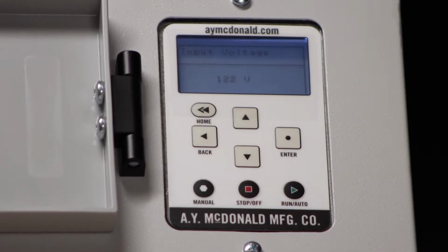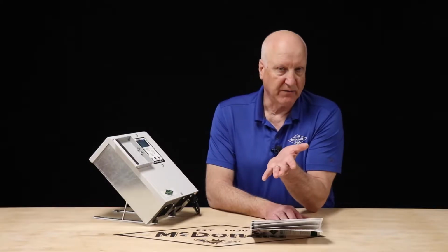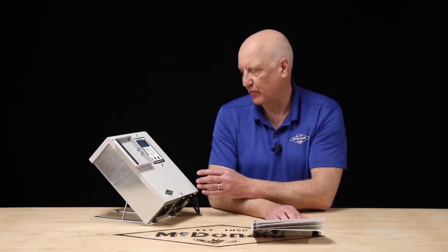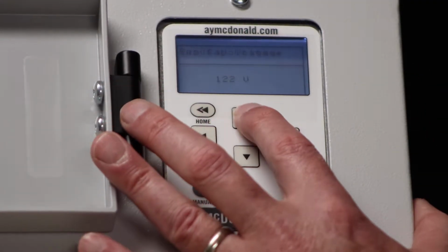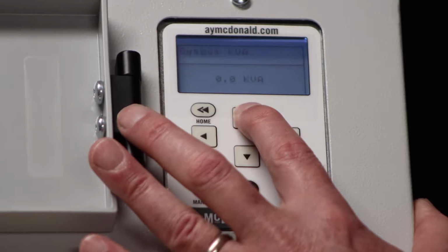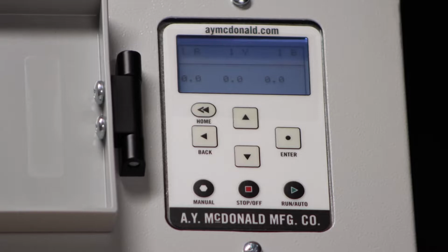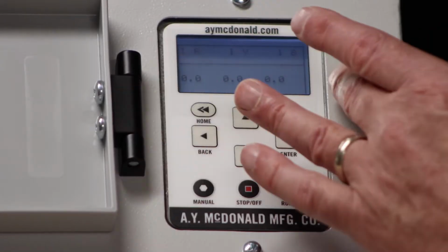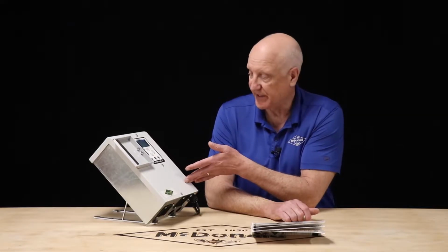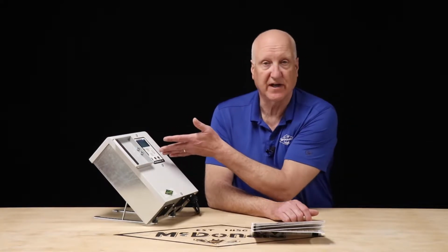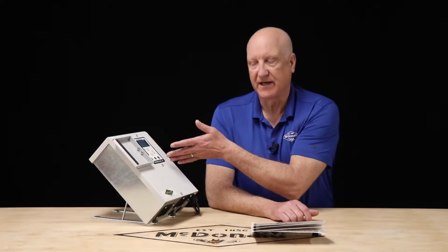The first one that comes up is the input voltage, and that's going to tell us the voltage coming to our system. Again, when we start troubleshooting, the two questions we ask are, what's your voltage and what are your amps? Right here it tells us our incoming voltage is 122 volts. Let's take a look at a couple other things in here. The bus capacitor, and here is the voltage. IR, IY, and IB tells us each leg going to our motor. This is a training demo, like I mentioned earlier. We don't have a motor attached. If we did have a motor running, it would tell us the current going to each leg of that motor.